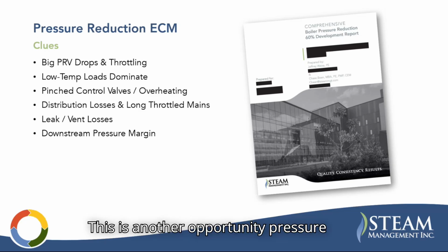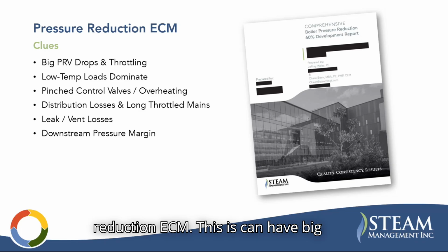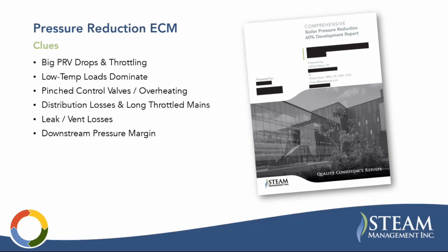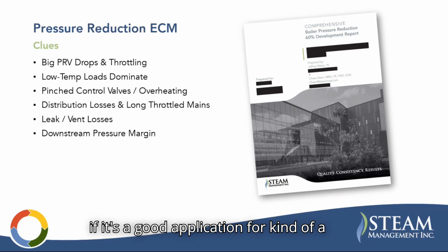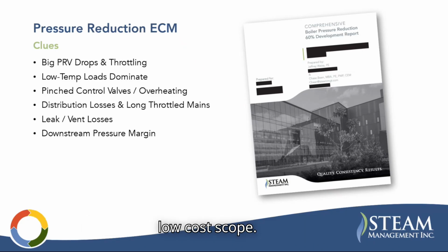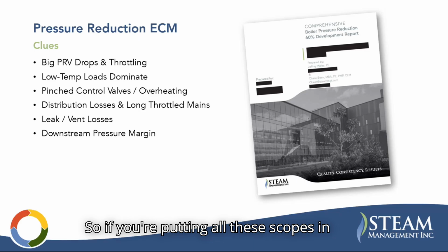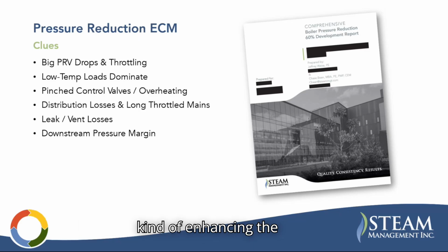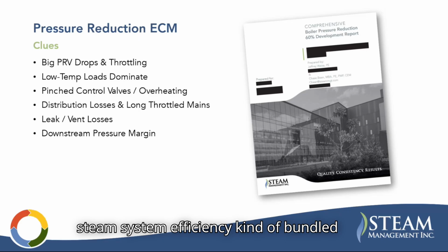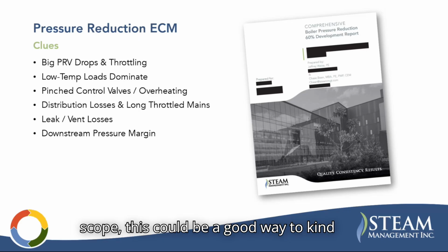This is another opportunity, the pressure reduction ECM. This can have big savings, like 2 to 8% if it's a good application, for a kind of low cost scope. So if you're putting all these scopes in, enhancing the steam system efficiency as a bundled scope, this could be a good way to bump up your savings a little bit.